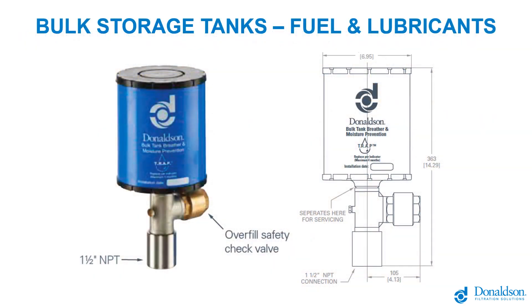Here we see the TRAP breather for large bulk storage tanks — same technology, just a larger format. On the left, you can see the installation kit along with the breather element. The bottom portion is a stainless steel T with an inch-and-a-half NPT connection to the tank vent, as well as a brass overfill safety check valve. On the right, you can see where the element separates from the installation kit for servicing — the black and blue portion is your replacement element.